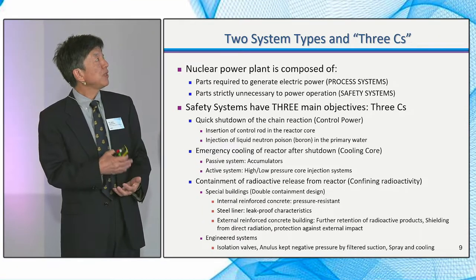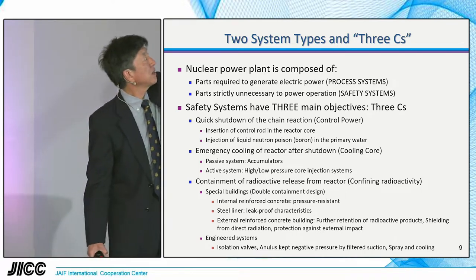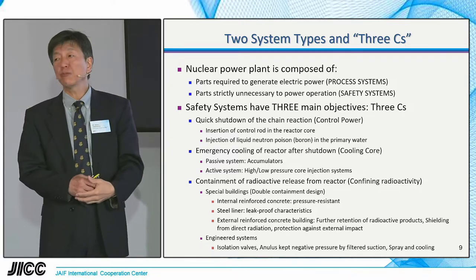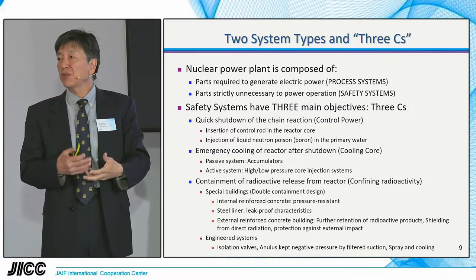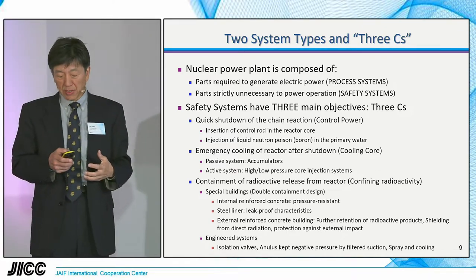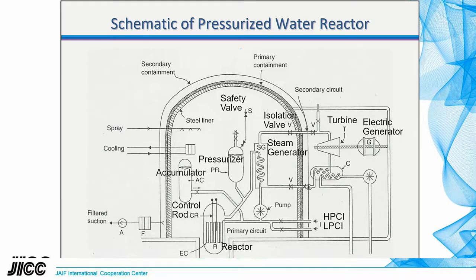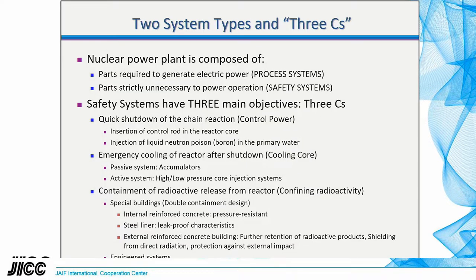The nuclear power plant is mostly composed of two types of systems. One is the process system — parts required to generate electric power; this is sufficient to generate electricity. However, nuclear power plants have many other systems. The reactor vessel and reactor core are important for power generation. Turbine, steam generator, primary and secondary systems are needed. But why do we have a containment vessel? This is the second type: parts strictly unnecessary for power operation — the safety system. In a nuclear system, the safety system has three main objectives: the three Cs.